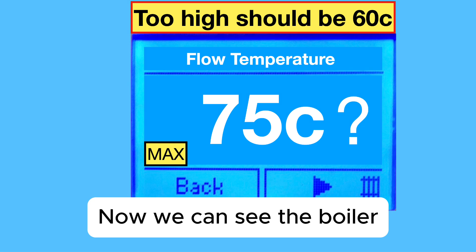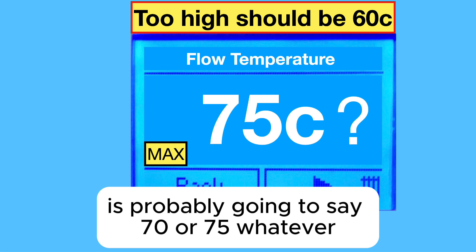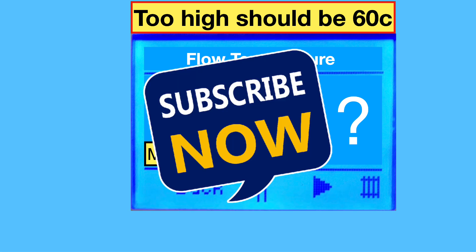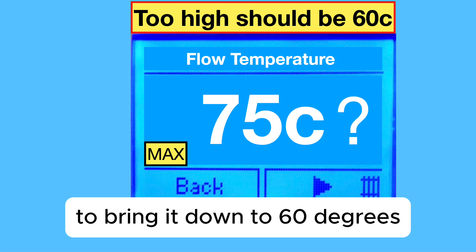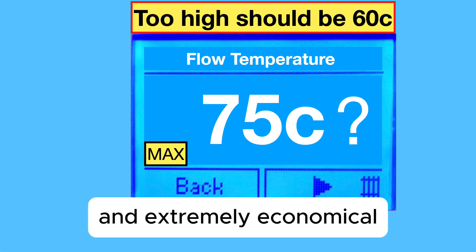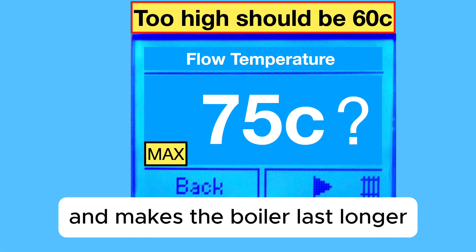Now we can see the boiler central heating flow temperature. It's probably going to say 70 or 75, whatever. But we're going to take a step-by-step guide to bring it down to 60 degrees, which makes it lean, green and extremely economical and makes the boiler last longer.